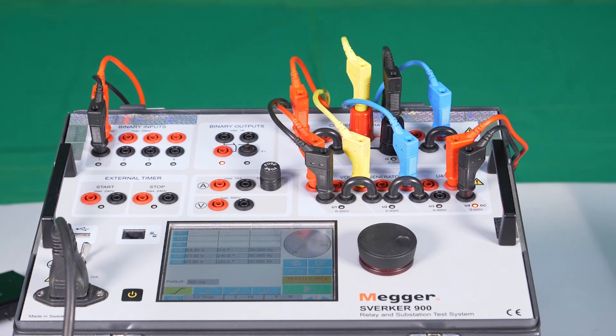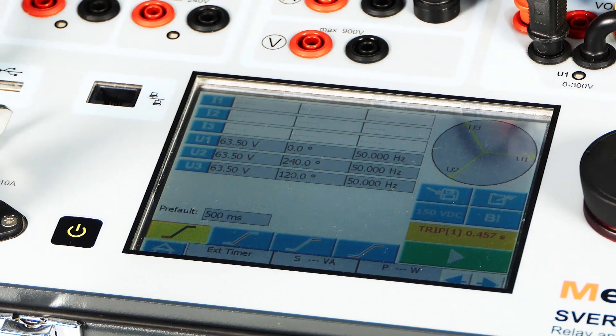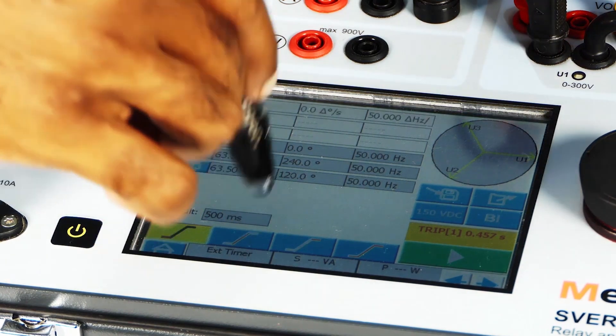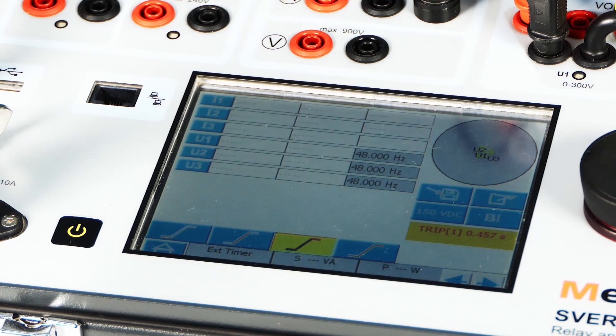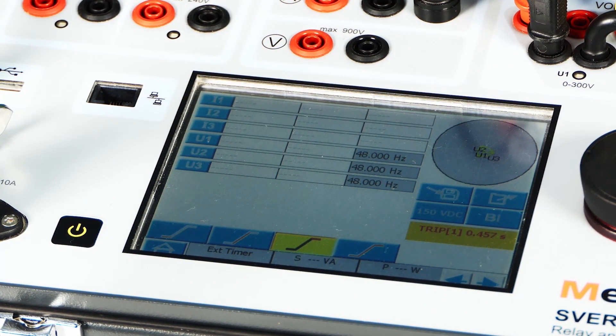In the ramping screen, the frequency is configured for 50 Hz as start value and a decrement of 0.21 Hz per second, and this value is decremented till 48 Hz.